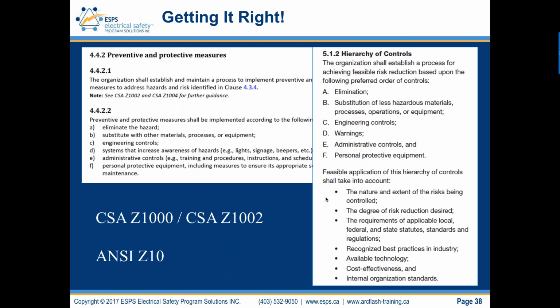The second hierarchy is substitution with other materials, processes, or equipment. So over time, we will install new equipment that is safer by its design. We'll substitute old equipment with new equipment. Right now, using arc-resistant switchgear is a substitution process, and there's a lot more of that happening. And for high-voltage power distribution equipment, I'm seeing a lot more gas-insulated switchgear as well. Then we move into engineering controls.